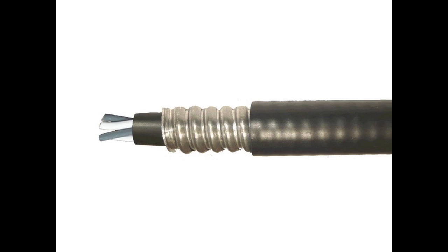TECK90 cables are constructed of stranded bare copper conductors with cross-linked polyethylene insulation and covered with a PVC jacket. There is armor over the jacket, which is then available with or without an additional PVC jacket over the armor.